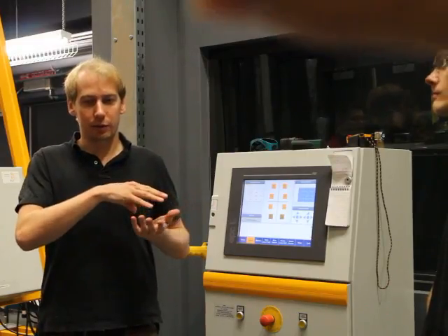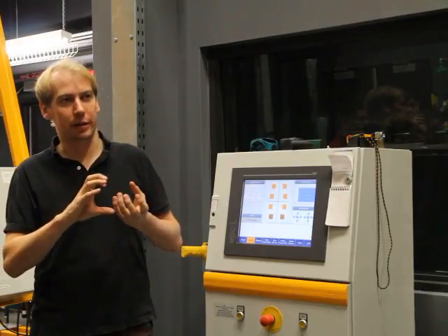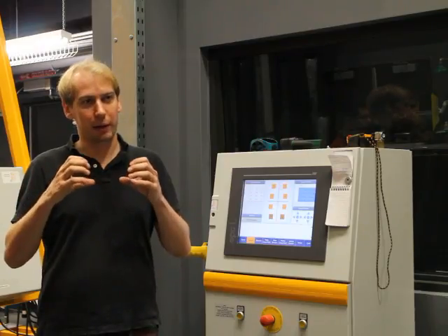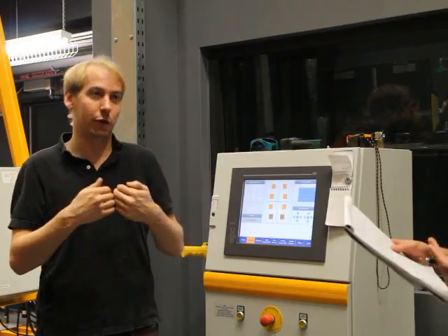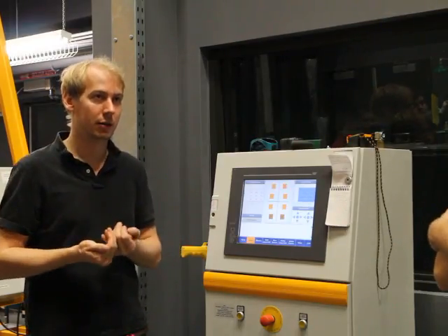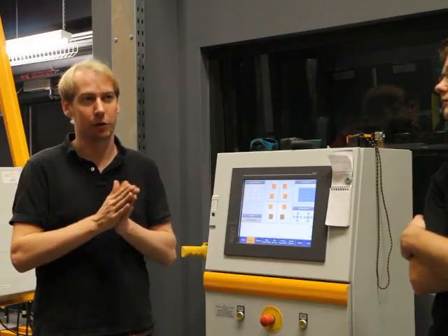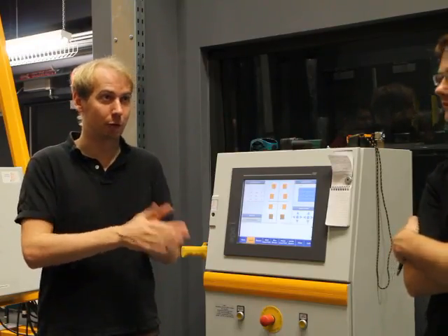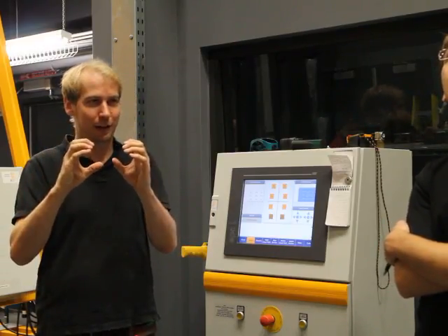As I already tried to explain yesterday, if you have different geometric shapes, like vacuum tubes, it can make sense to put the lamps a bit closer together, because then the portion of your direct irradiation gets higher. The standard for collector testing allows a homogeneity of plus or minus 15%. That's a lot. This is for thermal. For PV it's less.